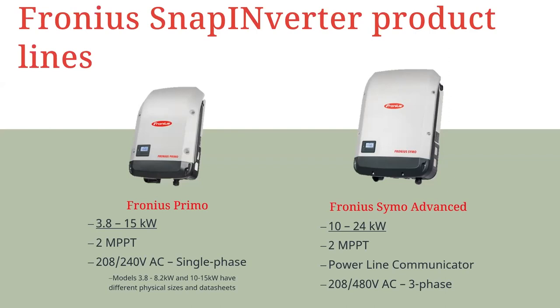That flexibility in terms of which voltage the system needs to operate on is really interesting and something that a lot of our customers really like. Can the Fronius Symo Advanced be configured for a 240 high-leg grid? Our Primo goes all the way down to 90 volts on MPP2. The 208-volt version of the Symo Advanced can be placed on a 240-volt high-leg delta grid — the L3 terminal will have the high leg on it, so it's important to note that.